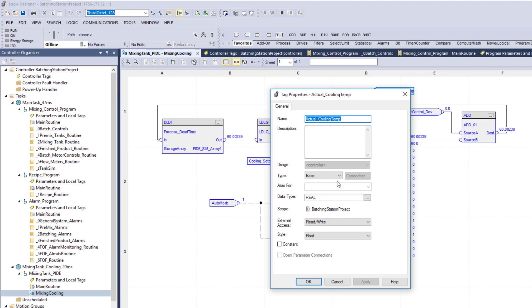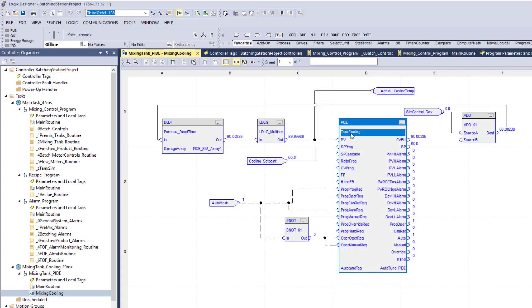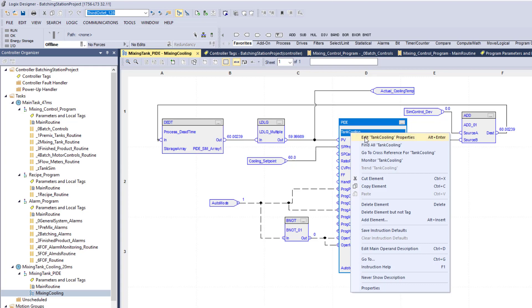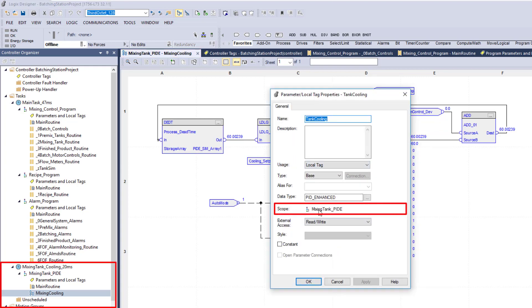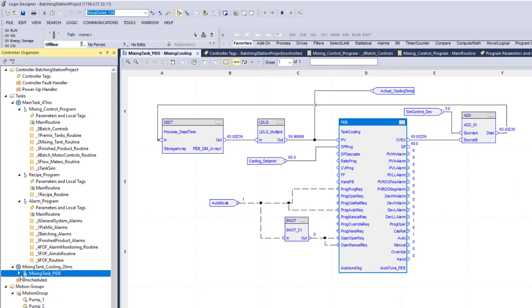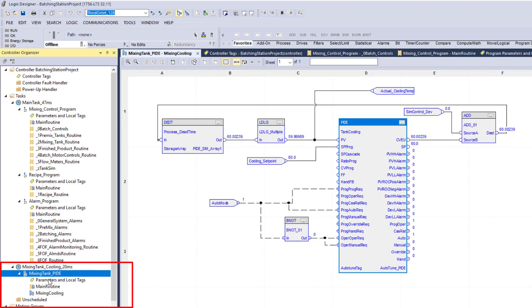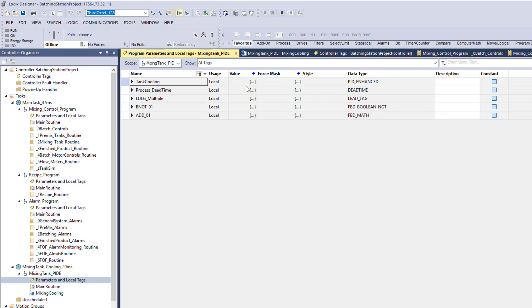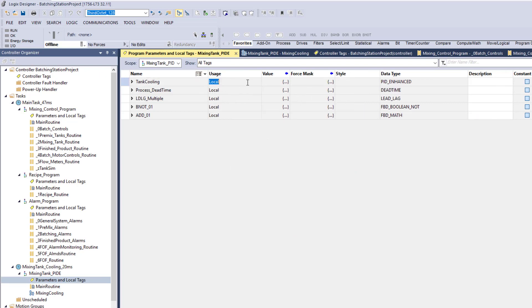This one right here is a controller tag — actual underscore cooling temp — looking directly at controller scope. And this one, tank cooling, is looking at the program scope. The program scope tag is going to be used locally only inside of this program called mixing tank PIDE. That is the only place it can be used. If I wanted to share it, I could use shared parameters or local parameters and change how these are utilized.